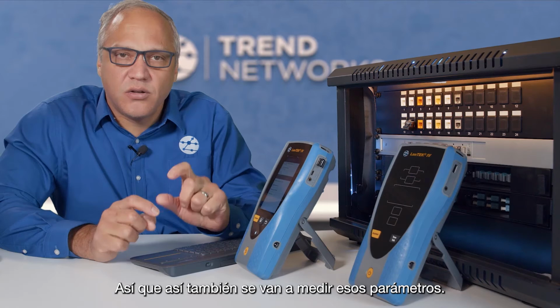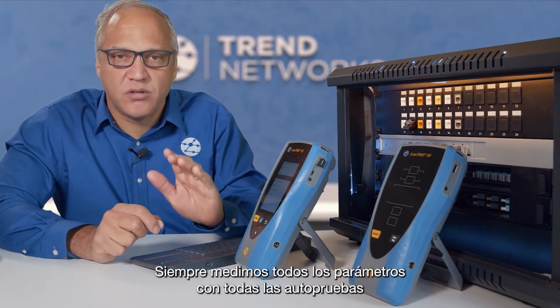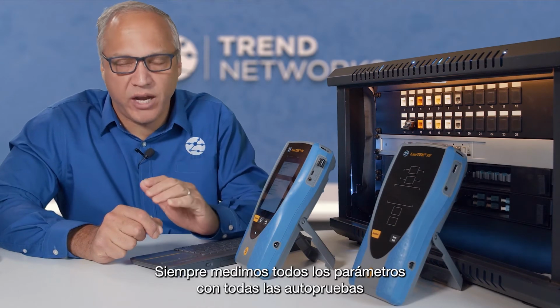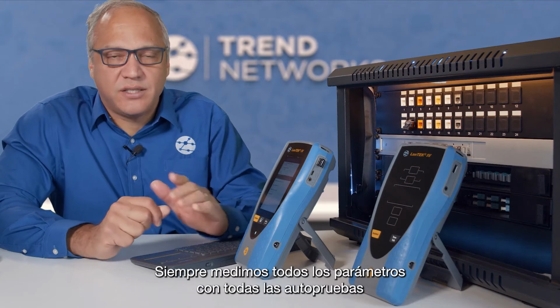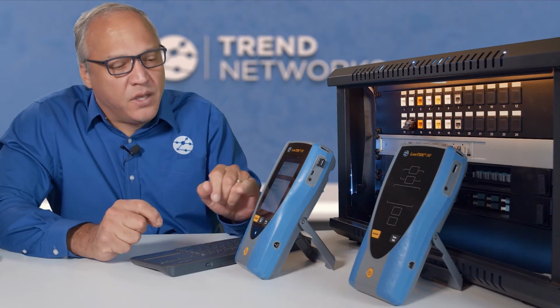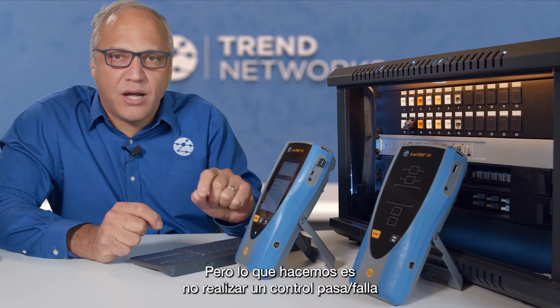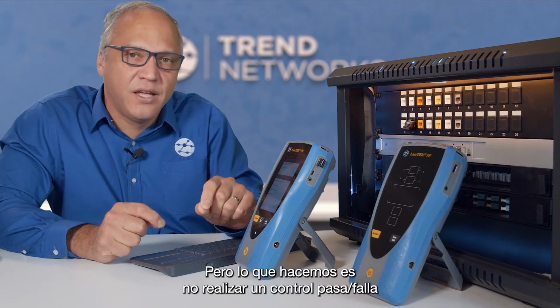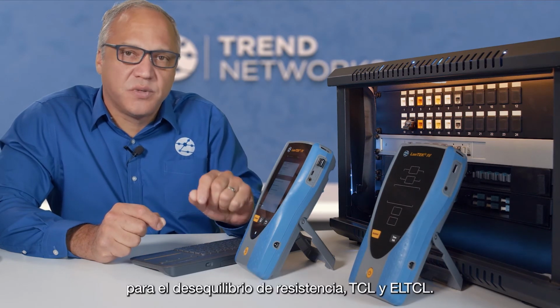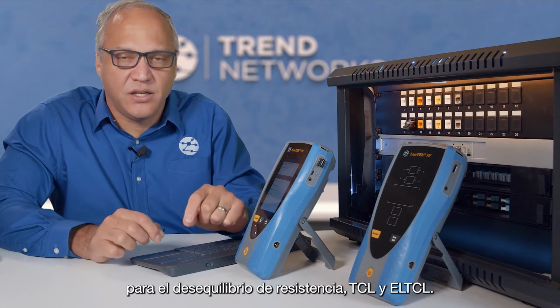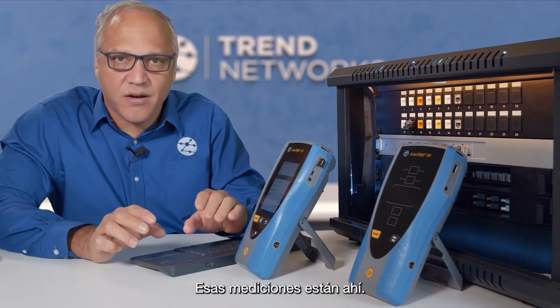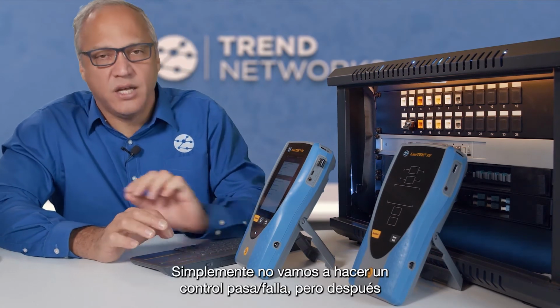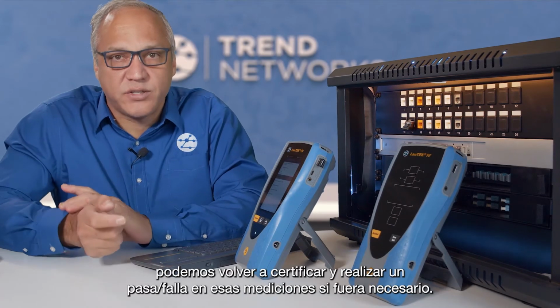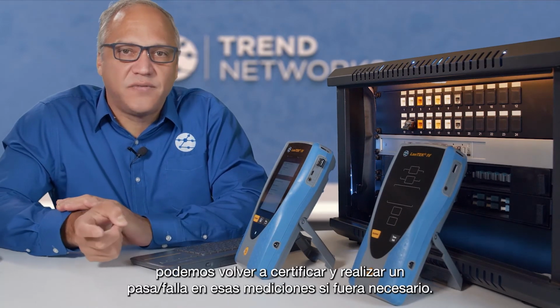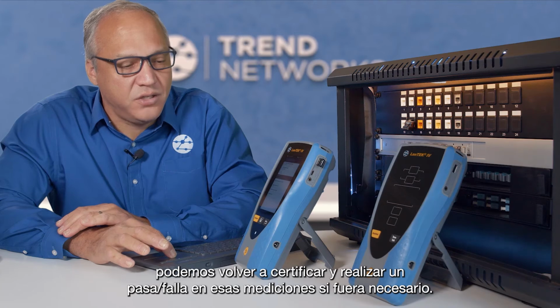So this is still going to measure those parameters. We always measure every parameter with every autotest, and that does not increase the test time. But what we're doing is not running a pass-fail check against, in this case, resistance unbalance, TCL, and ELTCL. Those measurements are there. We're just not going to do a pass-fail check, which means later on we can recertify and do a pass-fail against those measurements in the future if we need to.